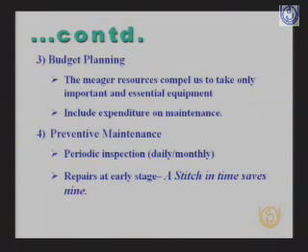The workload in terms of inpatients, outpatients, and ICU would help in assessing the requirements. How much budget do you have? Just because you have the money, you should not buy equipment, as I gave you one example. Whenever we buy these high-cost, sophisticated equipments, we have to include the expenditure on maintenance, the annual maintenance contract. Many a time the warranty is over and we have no money for its annual maintenance.